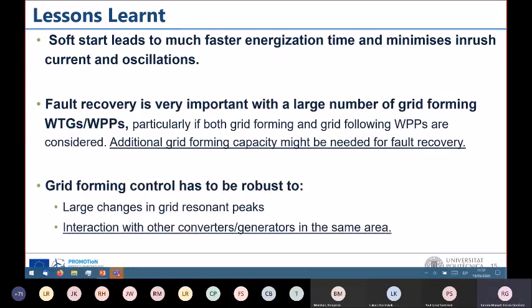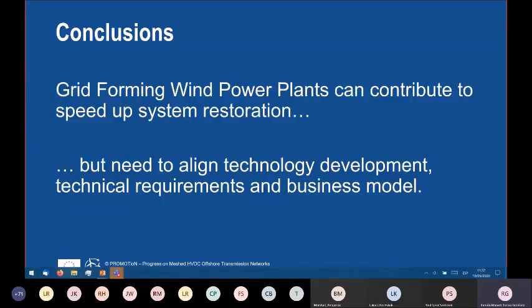And finally, controls for black start operations have to be very robust. They're going to operate in islanding mode and in a very changing configuration of the grid. So we need to be very robust to changes in grid topology, which can lead to different resonant peaks. We have to be aware that we might have interaction with other converters and generators in the same area. And what is the main conclusion? The main conclusion is that grid forming wind power plants can contribute to speed up system restoration. However, we need to align the technology development and the technical requirements, because some technical requirements might stop this from happening, and also provide a business model to be able to pull the technological development.